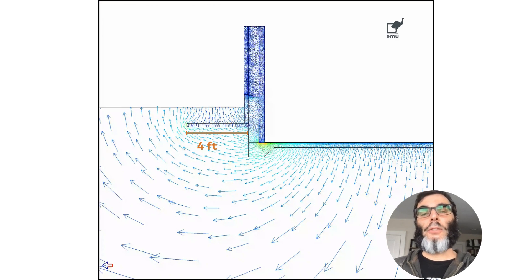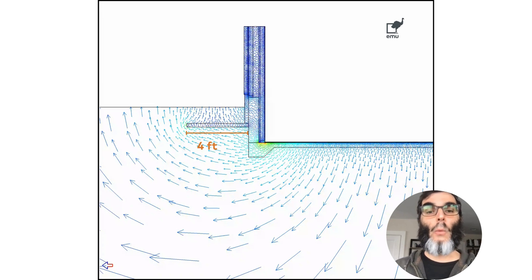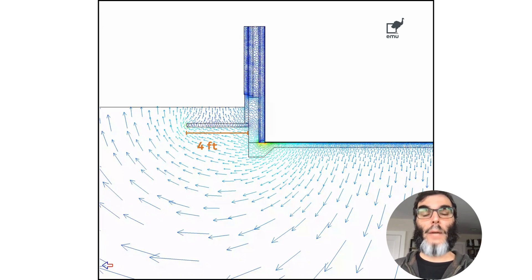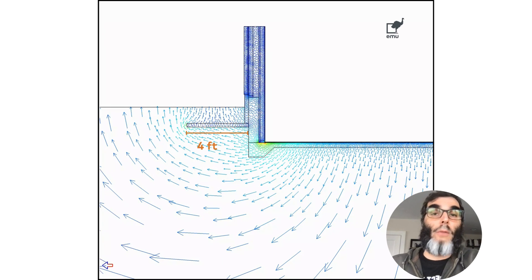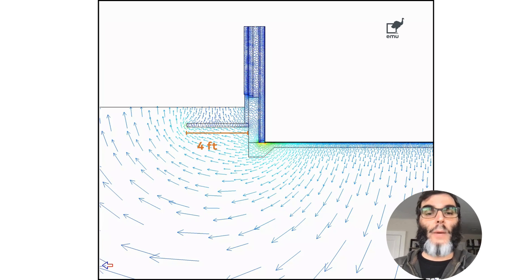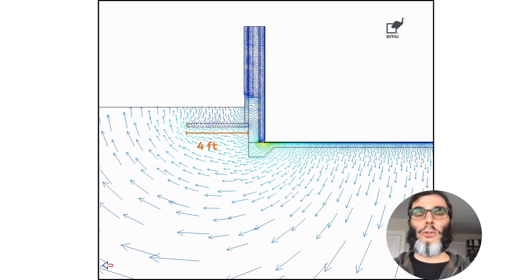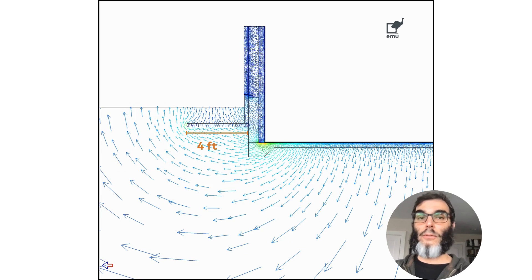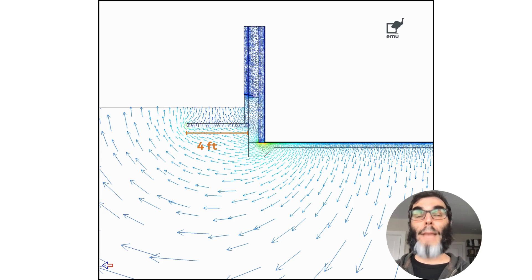If we extend that skirt insulation further out — previously it was two feet, now it is four feet — we see that the path of the heat to get to the outside is even longer. This is probably a more viable option compared to going all the way down to the footer or going over the slab with insulation. What is important is to have a scientific approach to this. This analysis shows better results than just having two feet of exterior skirt insulation, but it may still not be enough depending on your climate and type of building.